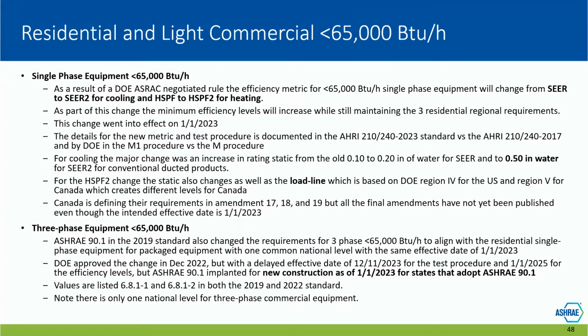For the three-phase, so all of those changes went into effect on 1/1/2023, and that's a mandatory change. We no longer can sell SEER products. Everything had to go to SEER 2 and HSPF2. So that really was a huge change for the industry. Three-phase, typically what we like to try and do, they're controlled directly by ASHRAE. So we updated the efficiencies, but DOE has to approve it, and they didn't approve it in time. So really, three-phase does not go into effect until January 1, 2025 for all equipment.